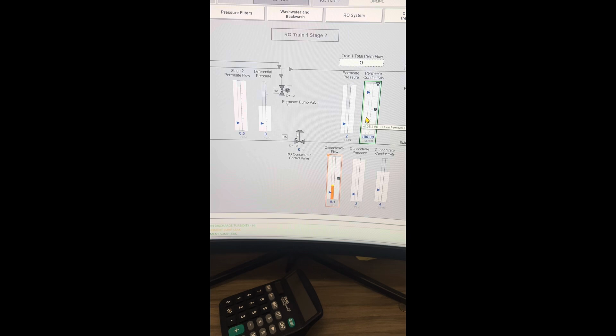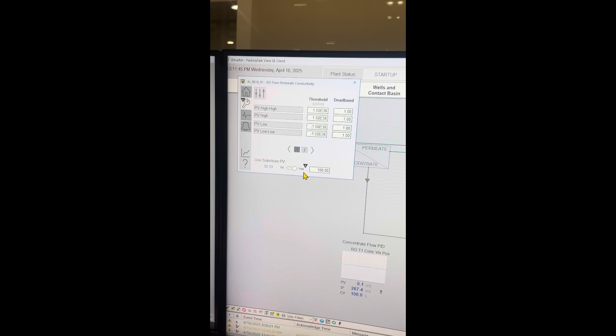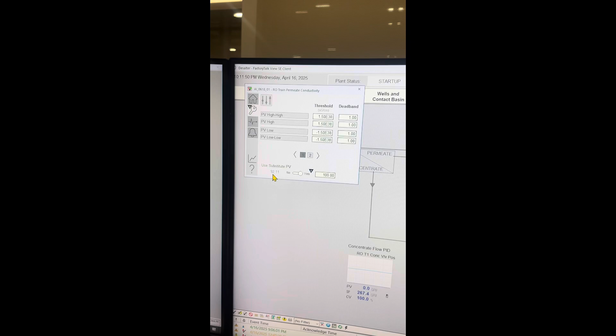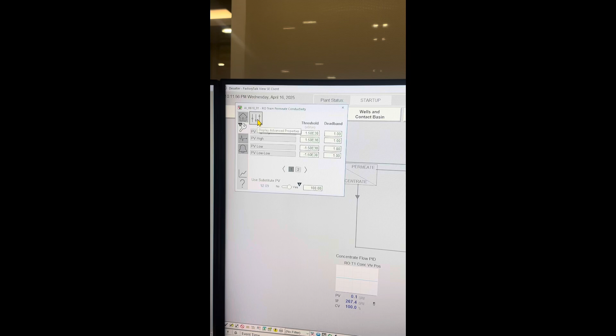Still on the same page, I'm going to go ahead and double click on permeate conductivity. I'm going to go ahead and hit the wrench icon. And as you can see, we still have the value of 100 for the substitute value, and the actual perceived value right now is only 92 microsiemens, and that's because, again, it's the scaling. So we have to change it in here.